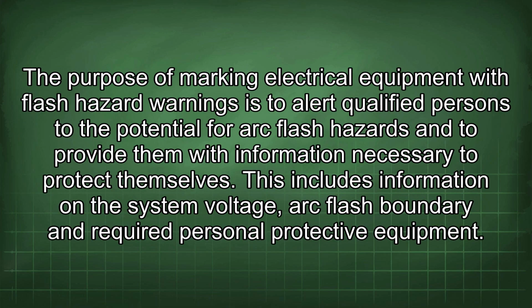The purpose of marking electrical equipment with flash hazard warnings is to alert qualified persons to the potential for arc flash hazards and to provide them with information necessary to protect themselves. This includes information on the system voltage, arc flash boundary, and required personal protective equipment.